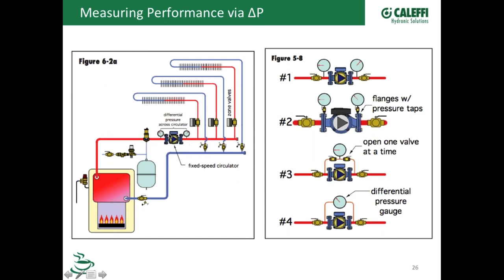And with that number, and I'll show you in the formula next, you can figure out how much flow this pump is moving through the system, how many gallons per minute. Now, a couple ways you can do this. You can put a gauge on both sides, like we showed you here.